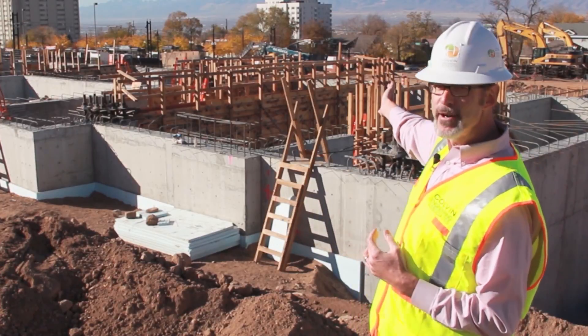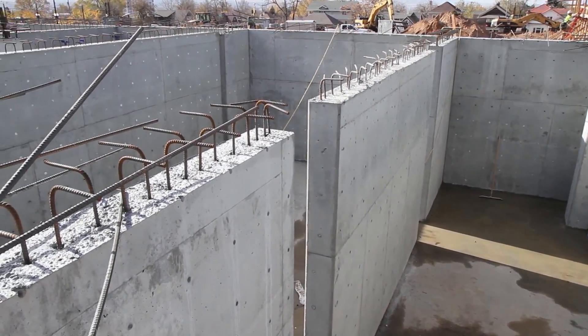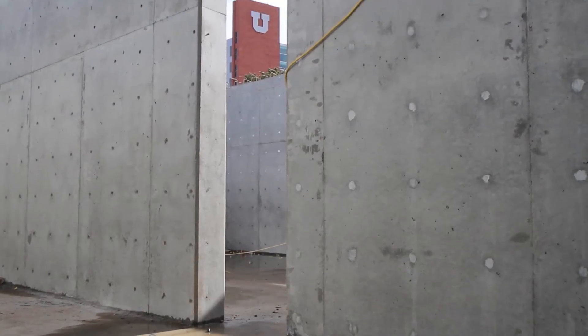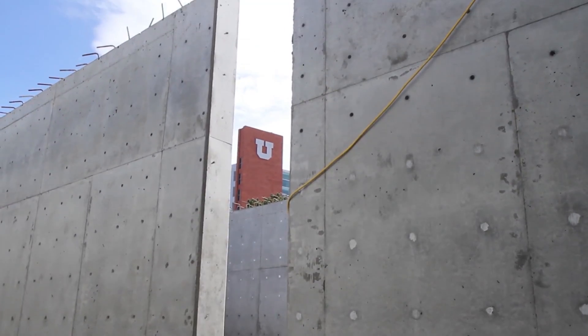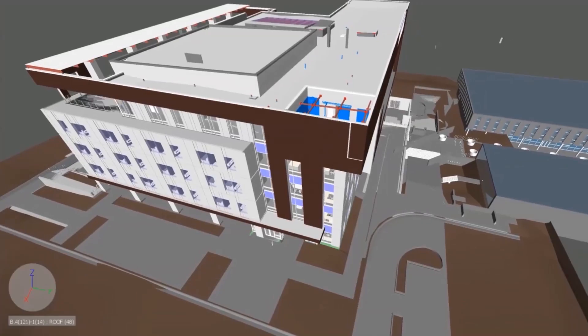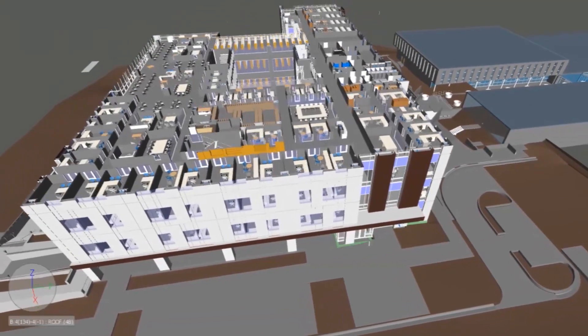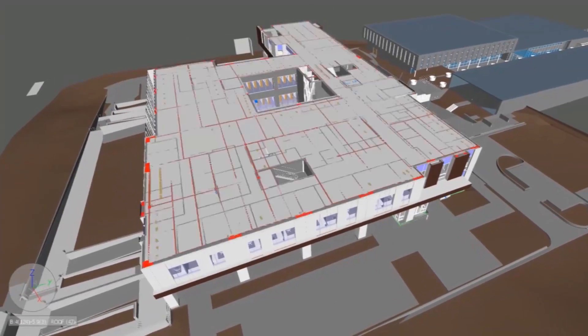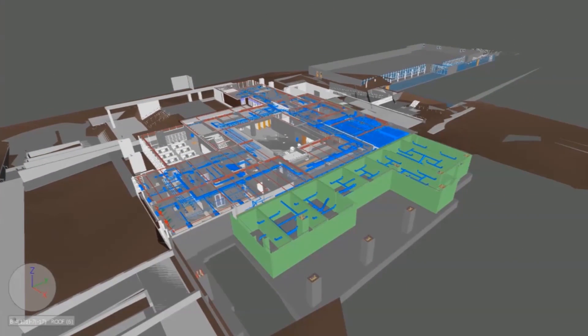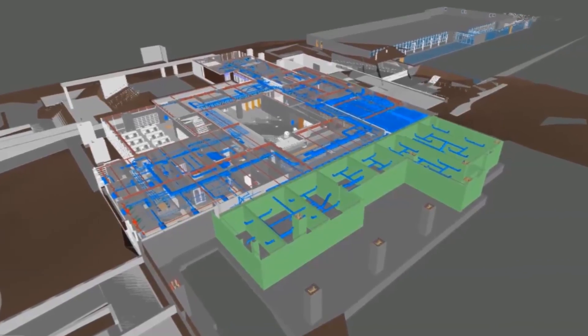What we do is take the irrigation water at night, pull it off, pump it, and store it in this tank right here. It's 400,000 gallons — almost as big as an Olympic-sized swimming pool. We store that tank full of cool water all night long. Then the next day, when the irrigation system turns off and sprinklers are off on campus, we pump water out of this tank and through our building to cool it. We did a lot of computer simulations and analysis to confirm this would work, and it works so well that we don't even need any kind of conventional air conditioning or additional energy to cool the building throughout the year.